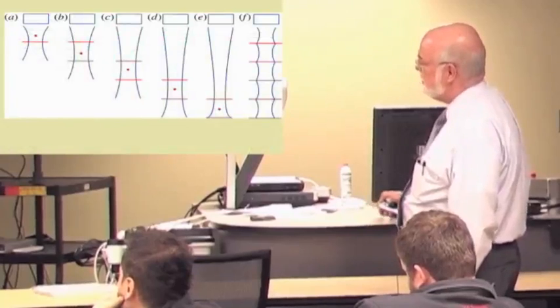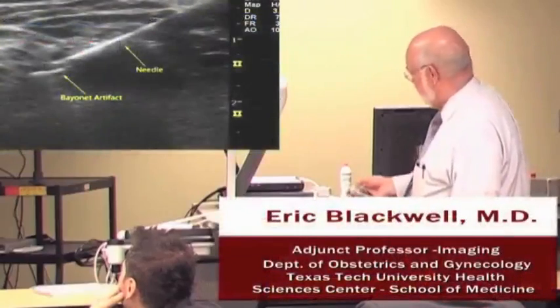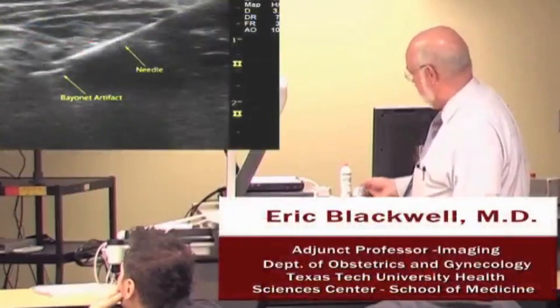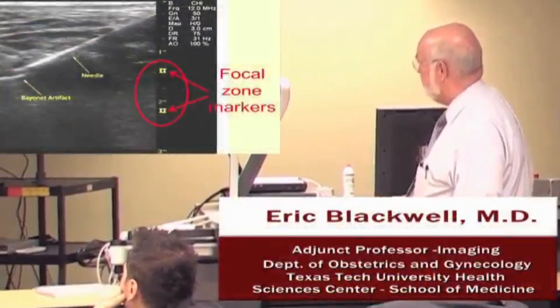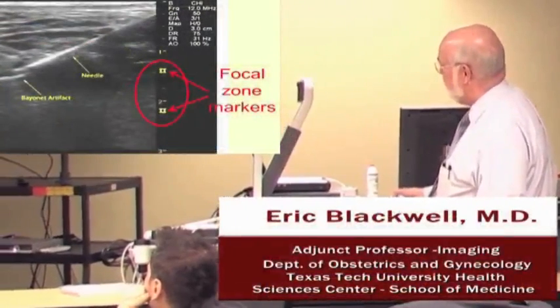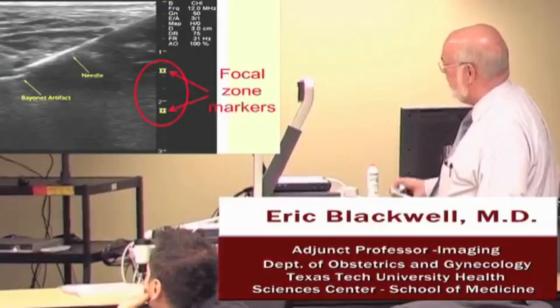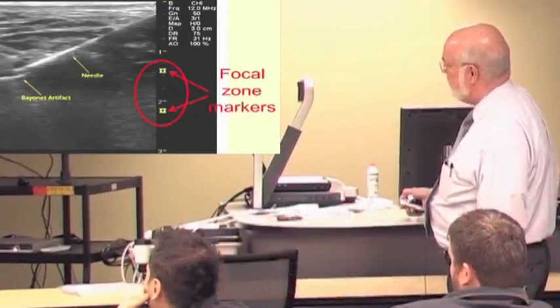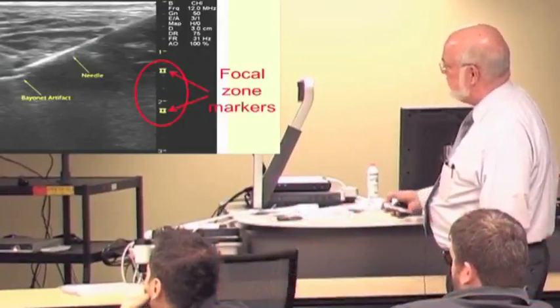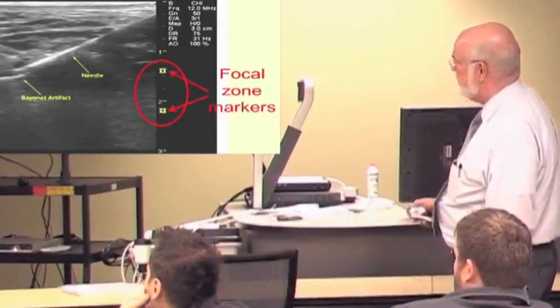Now, we can even have multiple focal zones, although the trade-off here is it slows the frame rate down because the computer is having to work harder. So, again, if you look at our example of the bayonet artifact here, what I want you to look at is actually the little displayed hourglass figures over here on the side, and that shows where the focal zone is set for this examination. And this is about right. It should be the distance between these should be somewhere in the area that you're most interested in.